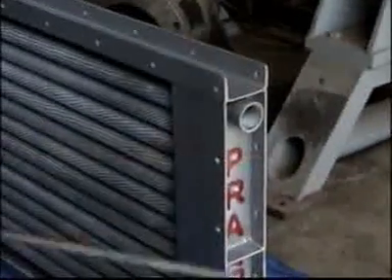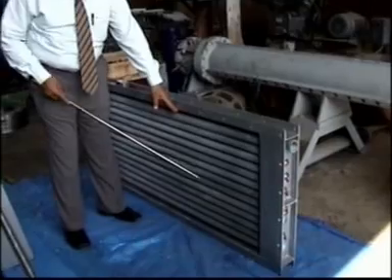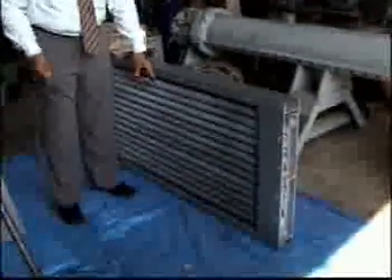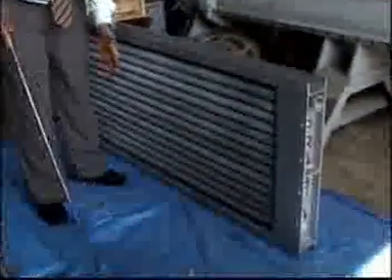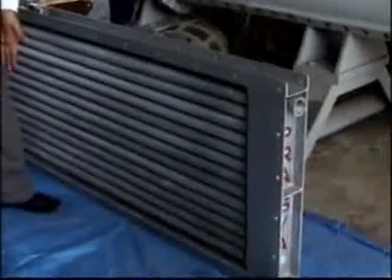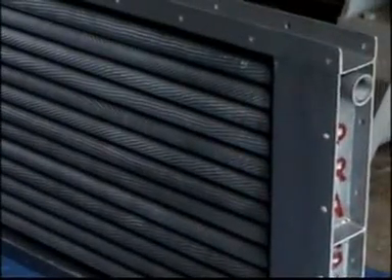This is a steam inlet. On the other side, there is a condensate outlet, and condensate will come out from that end. That steam will heat the tubes. These are the tubes. As I told you, this is the fin tube. From one side, you send the cold air through a blower, and on the other side you get the hot air for the dryer. So this is a conversion of cold air to hot air for dryer or cooler purpose.